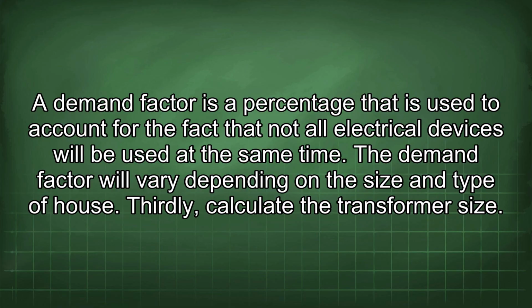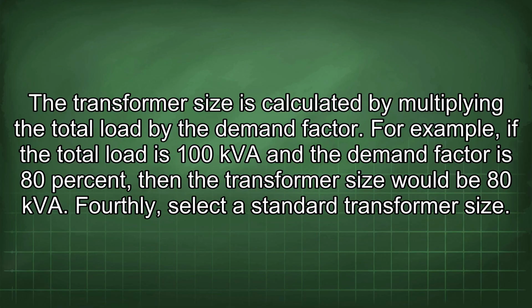The demand factor will vary depending on the size and type of house. Thirdly, calculate the transformer size. The transformer size is calculated by multiplying the total load by the demand factor. For example, if the total load is 100 kVA and the demand factor is 80%, then the transformer size would be 80 kVA. Fourthly, select a standard transformer size.